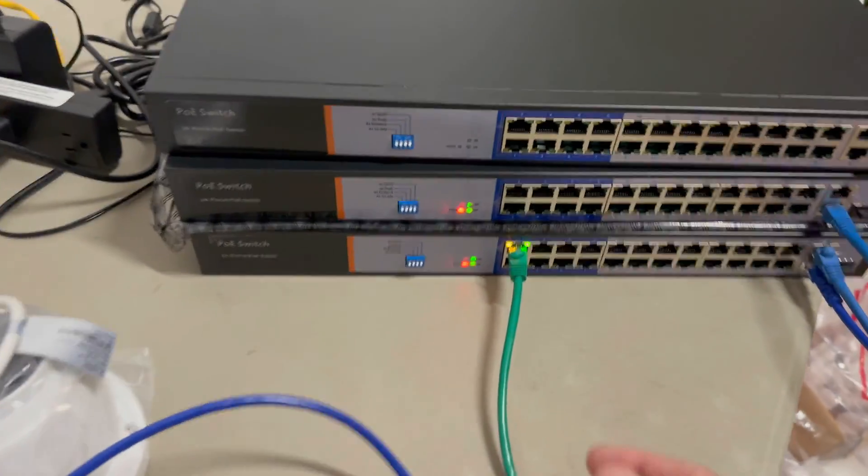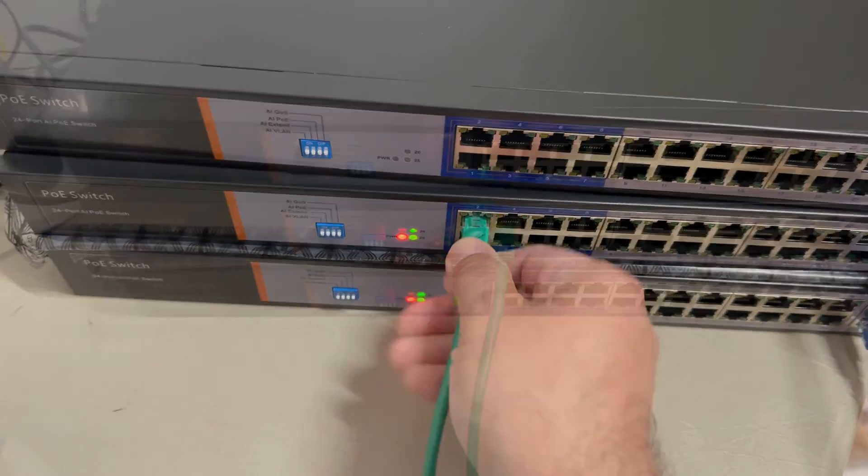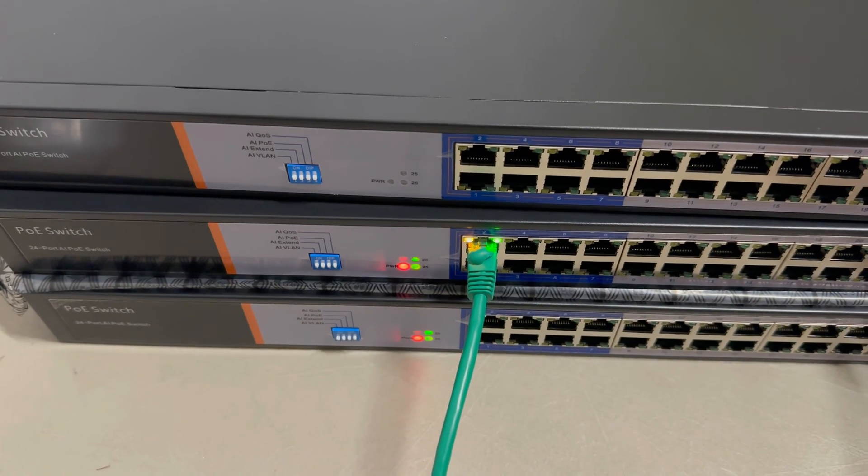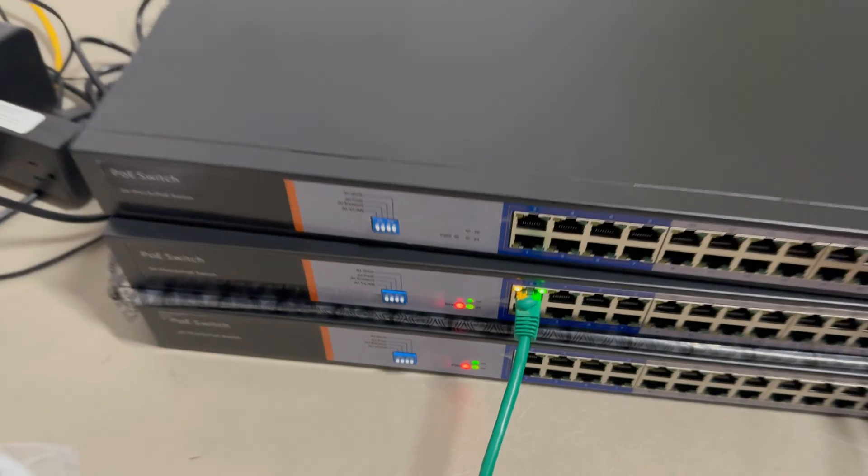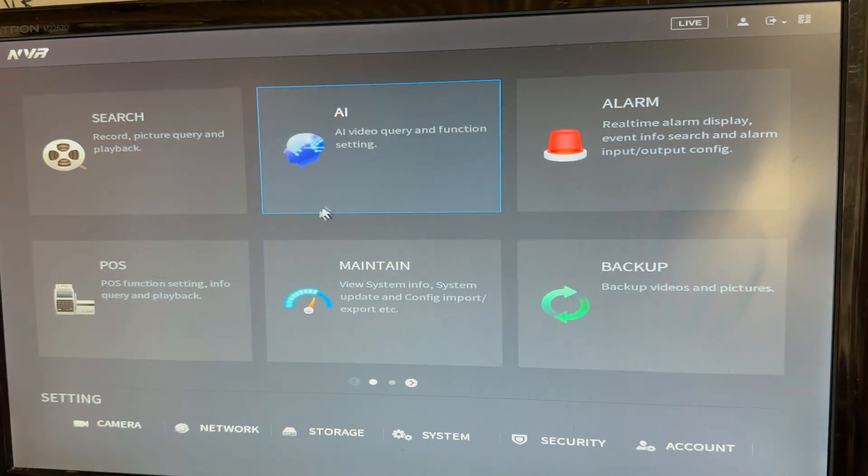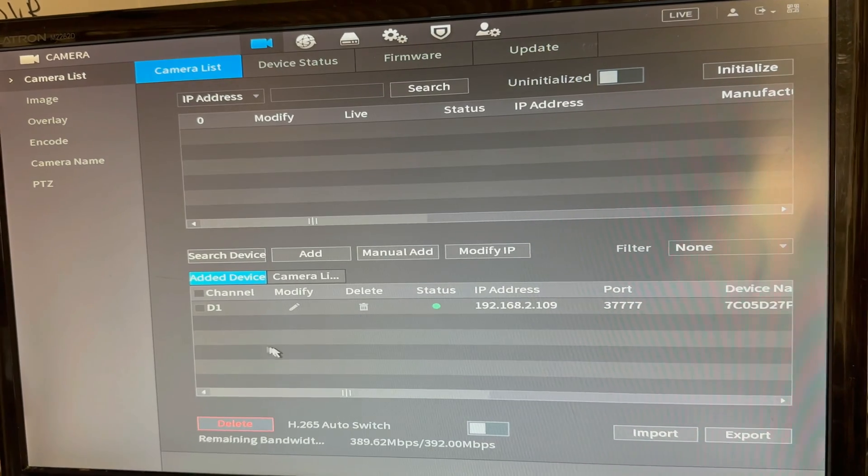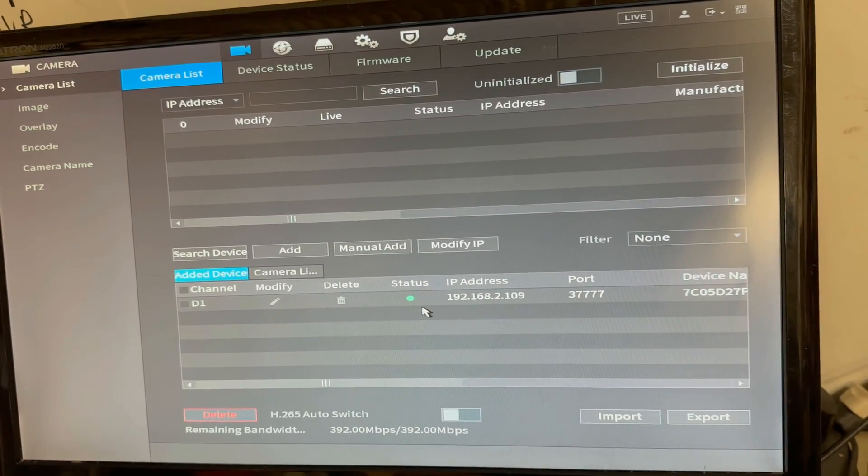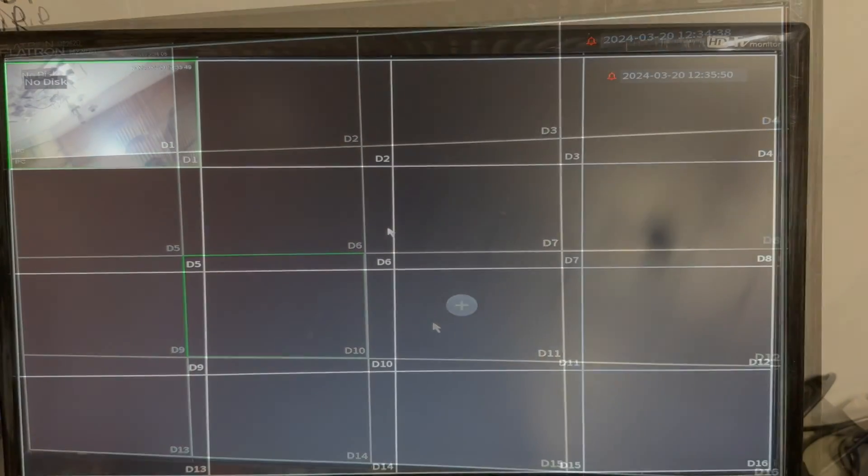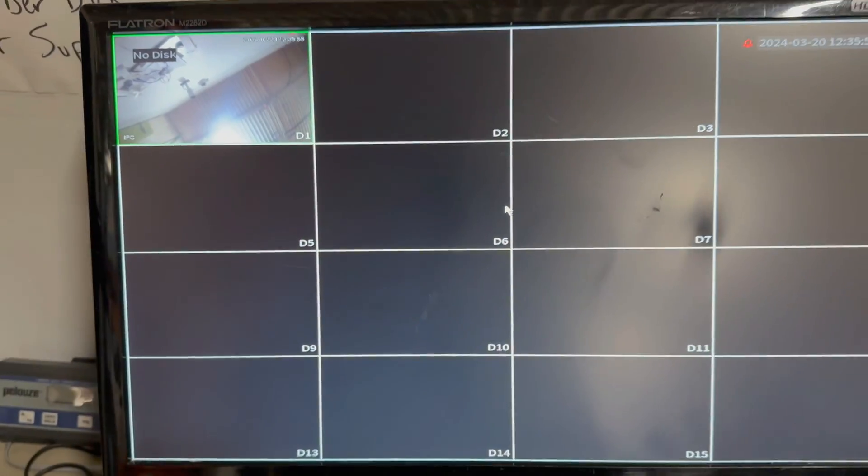Now, I'm going to take my camera, and I'm going to connect it to one of these ports. Wait a few seconds for the camera to light up, the data to start flowing through, the power to start flowing through. And I revisit my NVR to see if it's detected my camera yet or not. I can go into main menu, camera, and verify that this status signal is green. So it took about a minute and a half for the camera to start restreaming, and here we go. I just had to wait. So the camera has to fully boot up and for the data to flow through.